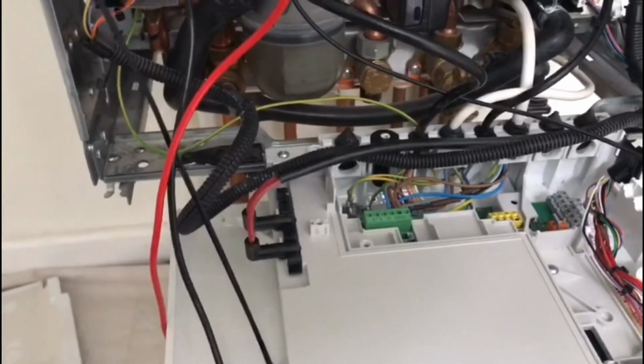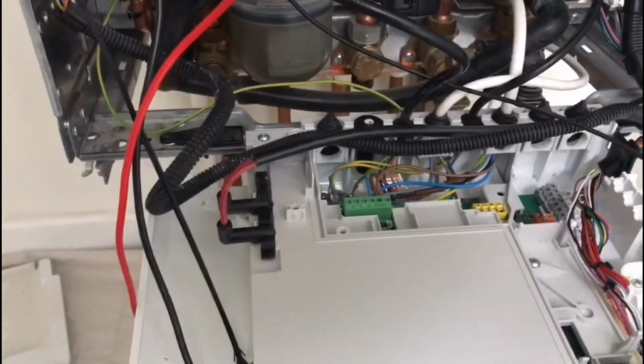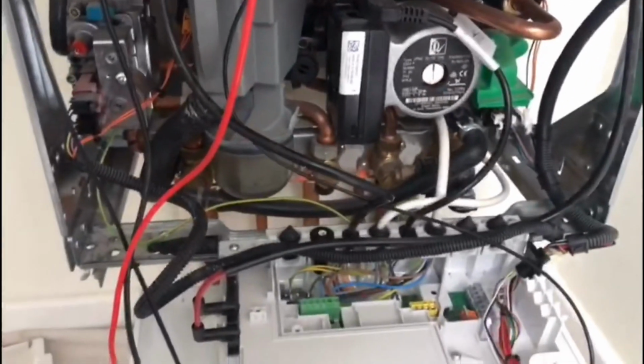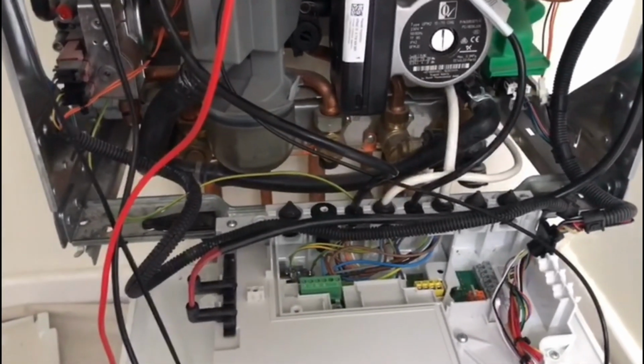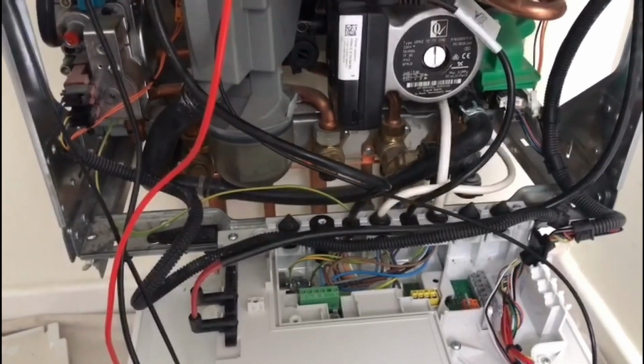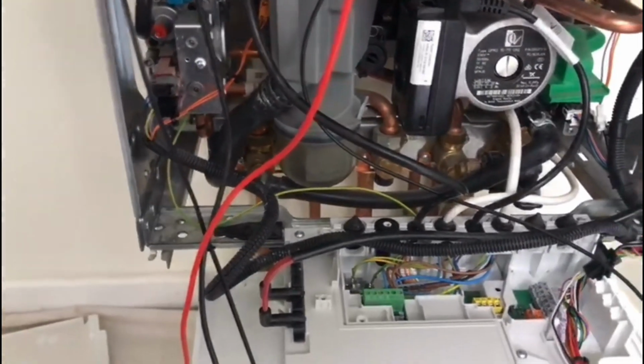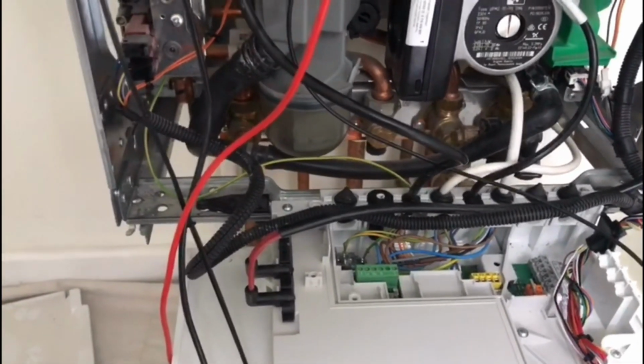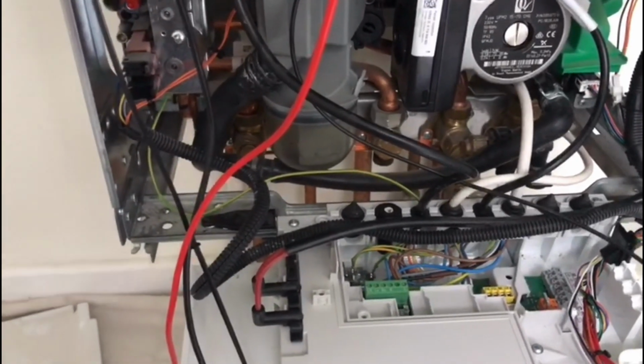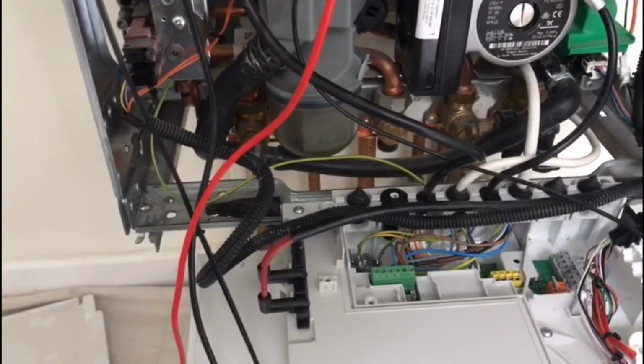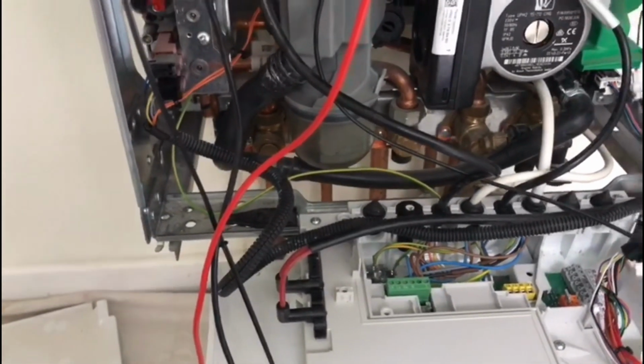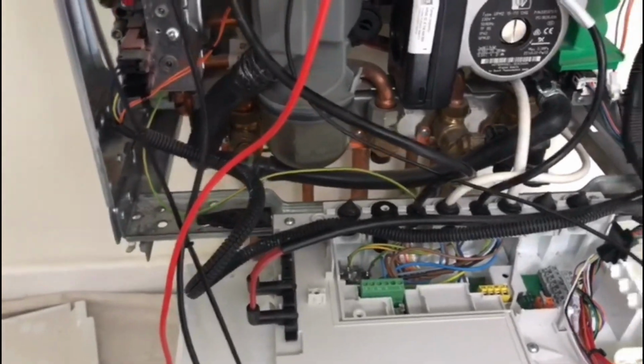There are variations on this test, as in reverse polarity. Reverse polarity is not a good thing for boilers. Some boilers will still work with reverse polarity, but the one problem you've got there is that the neutral is powered and not the live. So what happens there is that you would have no fuse protection on the fuse spur, because the current is passing down your neutral. So if it's passing down your neutral, it would go through the boiler, through you. If there's a problem and you're getting a shock, it wouldn't blow the fuse. The reverse polarity is a very important one to bear in mind.